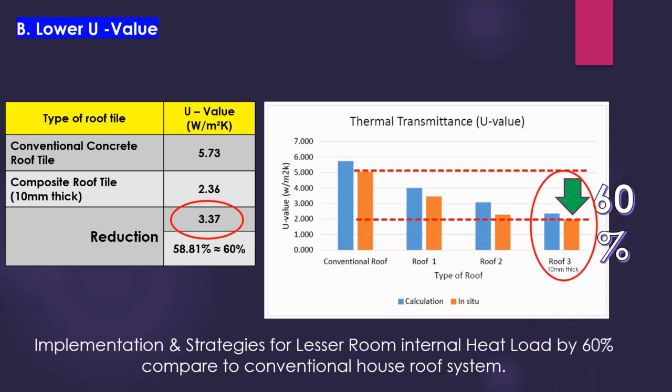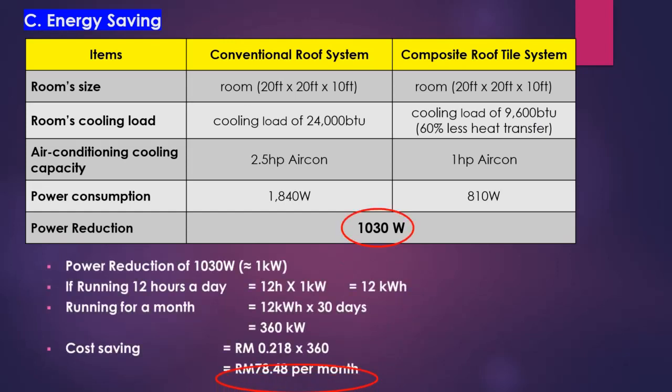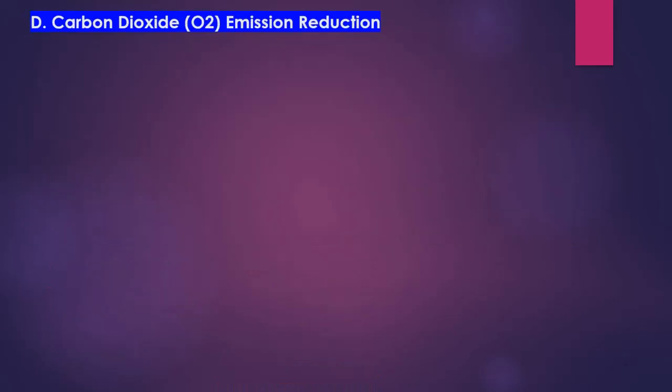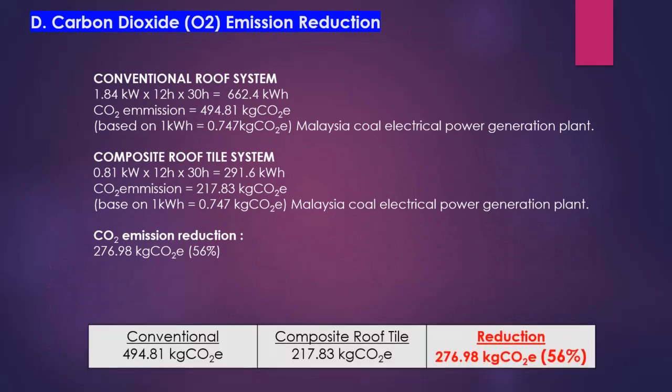The 60 percent heat load reduction results in an air conditioning power consumption reduction of up to 1030 watts, which may result in cost savings of up to 78.48 ringgit per month. The carbon dioxide emission reduction, comparing conventional to composite roof tile, is around 276.98 kilograms of CO₂ equivalent, or 56 percent.